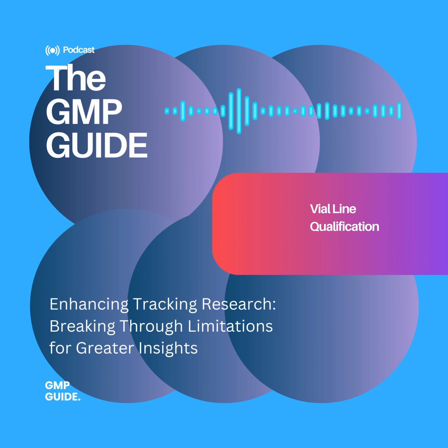Track 3.3: Performance Qualification, PQ. All right, so after all that meticulous installation and operational qualification, where every component and its function has been rigorously tested, we arrive at Performance Qualification, or PQ. This is the final and perhaps most critical step in equipment qualification. It's where the team verifies and documents that all user requirements are consistently met, ultimately confirming that the equipment and entire systems are truly fit for intended use, as defined in the user requirement specification. The final proof. This only proceeds after successful IQ and OQ.